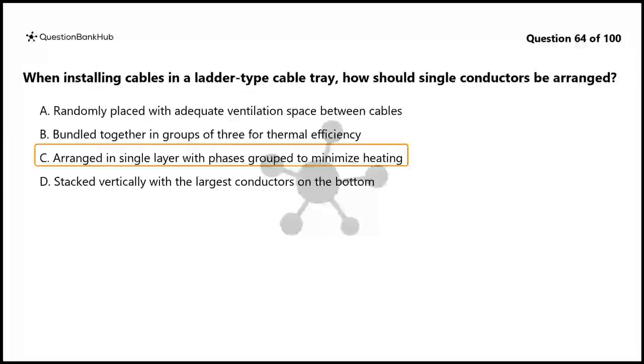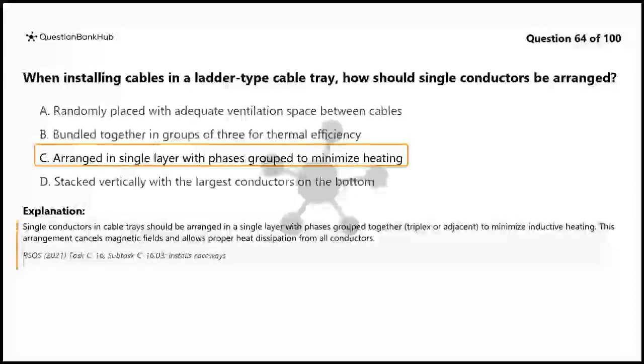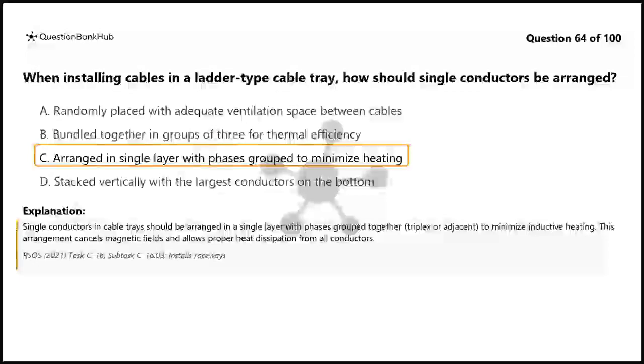The correct answer is C. Arranged in single layer with phases grouped to minimize heating. Single conductors in cable trays should be arranged in a single layer with phases grouped together, triplex or adjacent, to minimize inductive heating. This arrangement cancels magnetic fields and allows proper heat dissipation from all conductors.